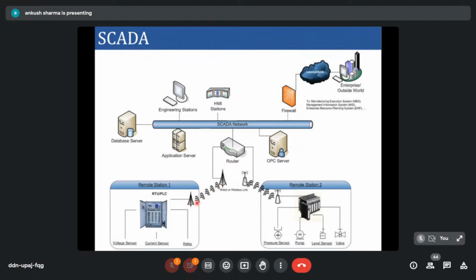The protocol we use for communication is IEC 60870-5-104 if you want network communication, or if you still have serial data communication, you use 101. Via the router, the data reaches the SCADA network. Here the communication medium can be anything: optical fiber, GSM, GPRS, or Wi-Fi. Depending on the distance of the device from the control center, you decide what kind of communication mechanism is required.